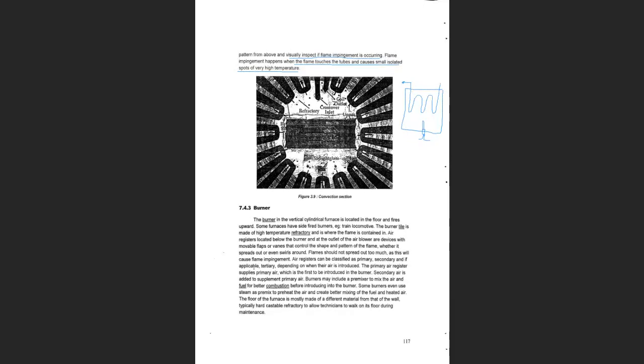احد اهم الاشياء يا اخوان اللي هو عشان كذا تتطلب انه يكون عندك فيجوال انسبكشن، انك تشيك من الداخل. طبعا ان شاء الله بوريكم بعد شوي شلون تشيك. يعني by the way you can have a window at the side of the firebox through which you can look at the firebox يا شباب and see the flame. واضح من اهم الاشياء يا اخوان انه for the safety of the coils and the furnace you have to make sure that the flame is not too long.